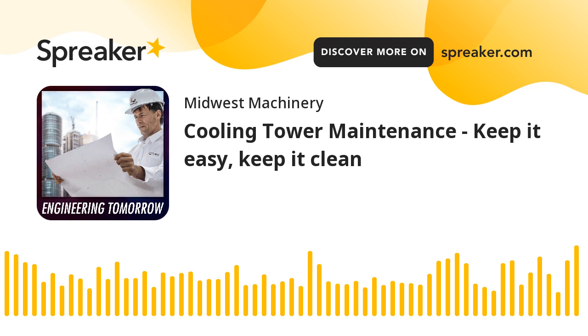You can install a basin heater system. Now this is for any manufacturer. They would have a basin heater. It's a probe that will go in there and maintain your water temperature at a certain level. Another one would be field installation of heat tracing of piping, both internally and externally, making sure that your piping to the tower and in the tower is heat traced, that you wouldn't have any freeze damage.